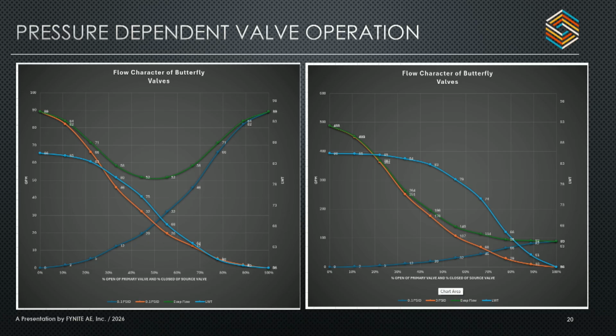When the pressure drop across the valves changes, there's an assumption made that you're going to have linear flow across your control valves. There are 2 butterfly valves on these systems that control net water flow into the inlet of the evaporator, for the heating and for the cooling needs. We all know that butterfly valves are not really linear devices anyways, but when the pressure differential across the valve gets great or different, you can have a significant flow variation.